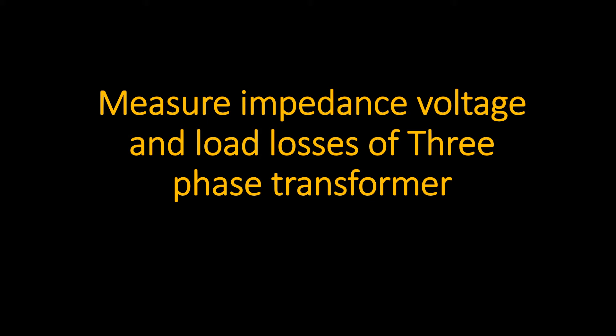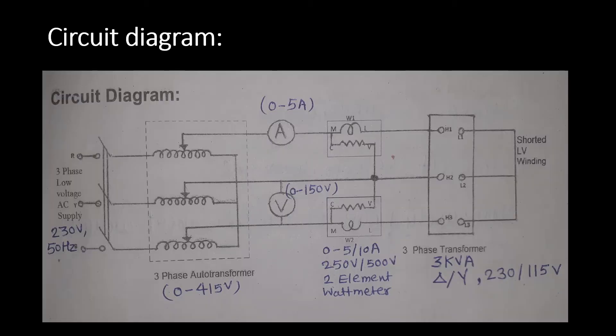We will measure impedance voltage and load losses of a three-phase transformer. Make the connections as per this circuit diagram. We are considering a two-element watt meter. The transformer under test is 3 kVA, delta-star connected — primary is in delta and secondary is in star. Primary voltage is 230 volts whereas secondary voltage is 115 volts.